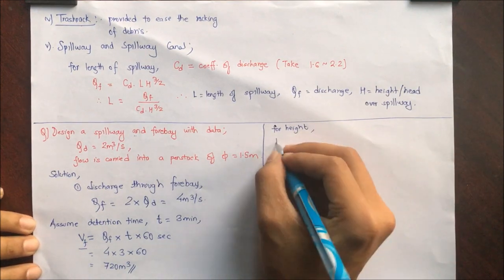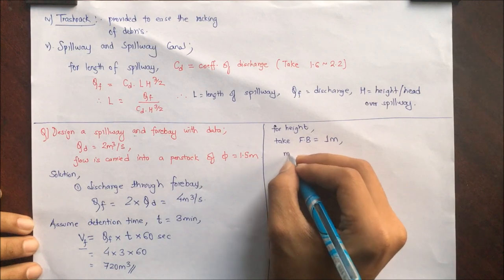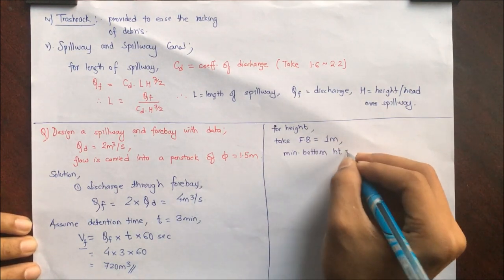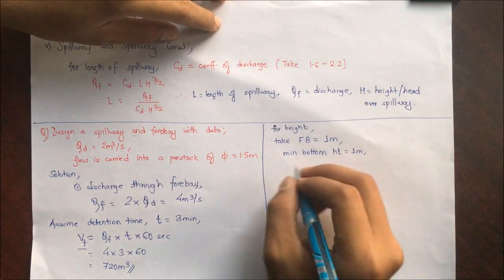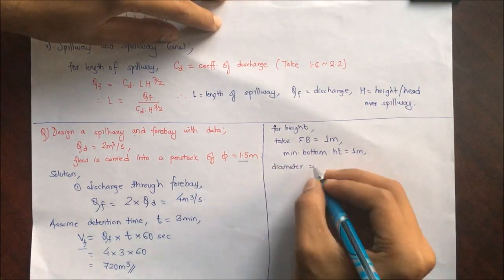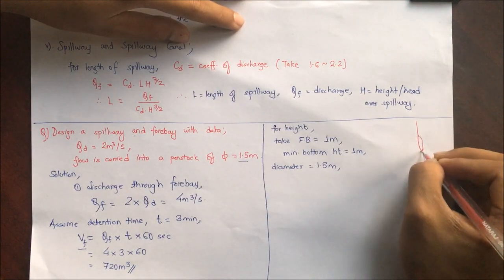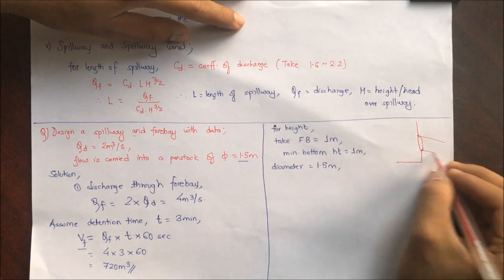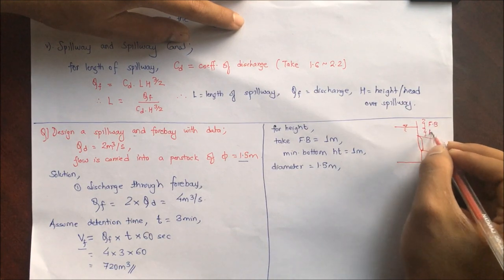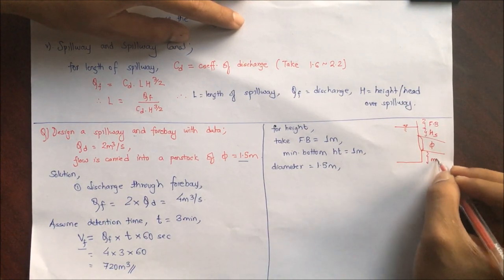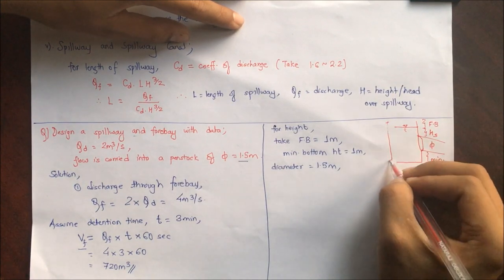For height calculation, taking freeboard as 1 meter if not specified, and minimum bottom height (settling height) as 1 meter. Diameter D is 1.5 meter as provided. We can draw a figure showing the penstock portion: freeboard of 1 meter at top, then H as submergence height, then diameter of penstock, and minimum settling height for sediments at the bottom — giving total height H.